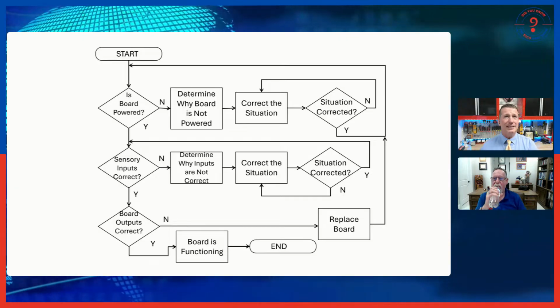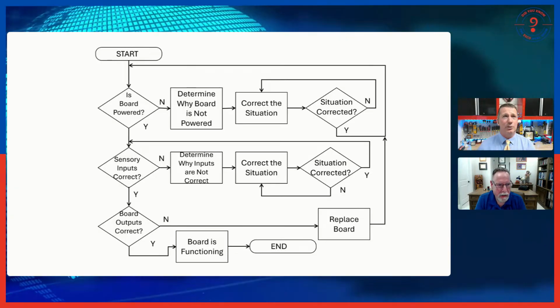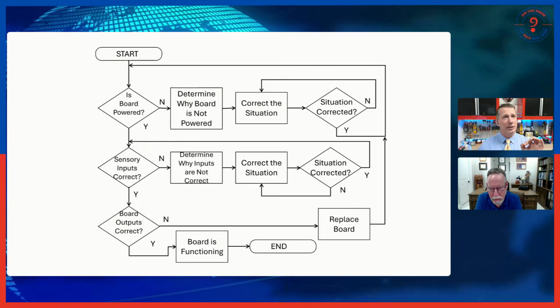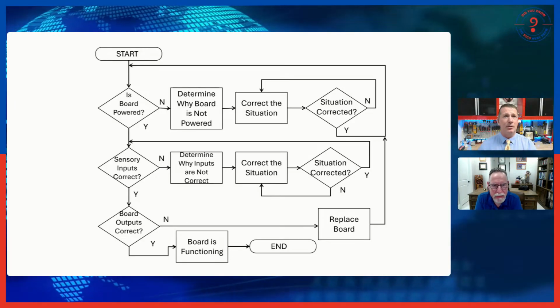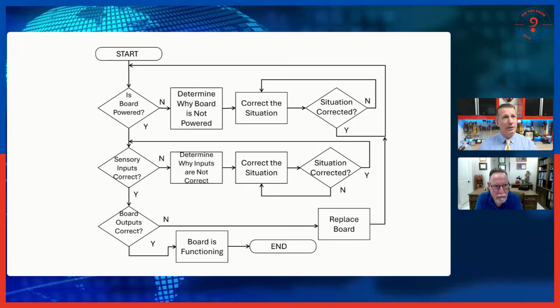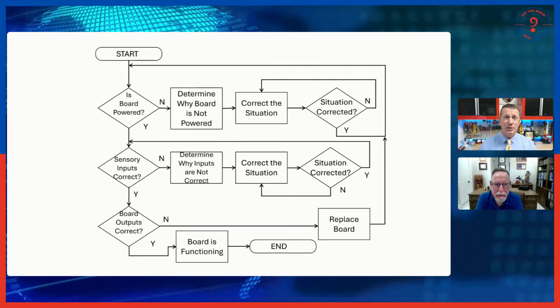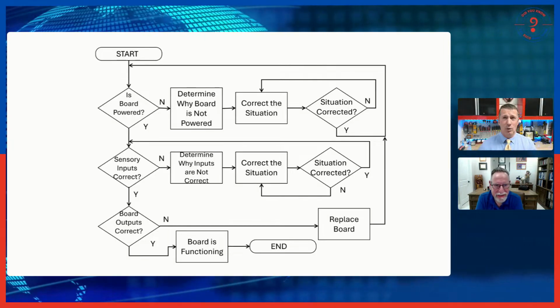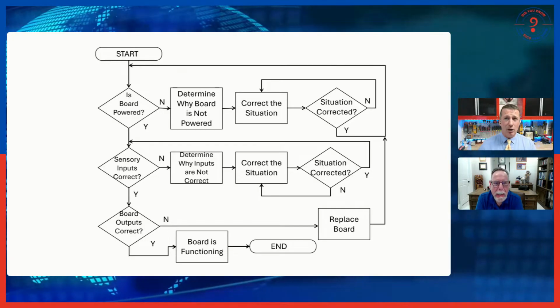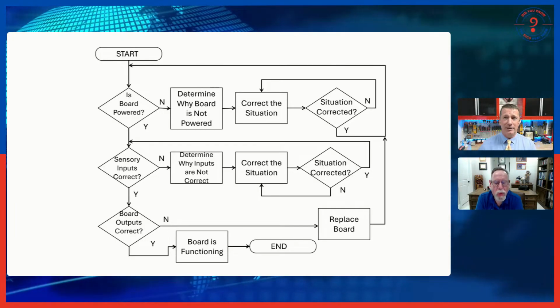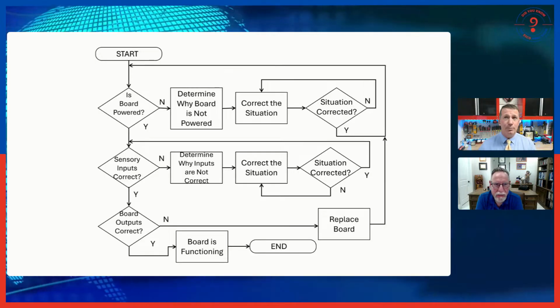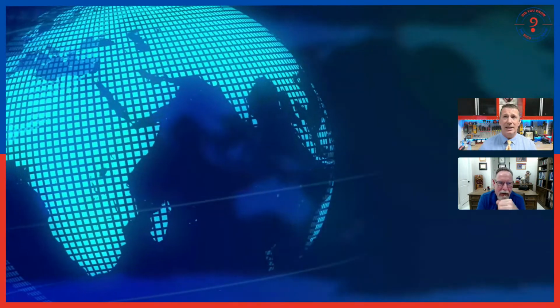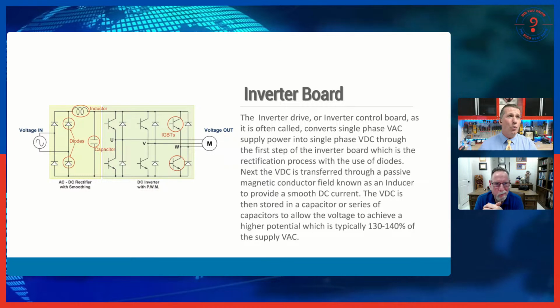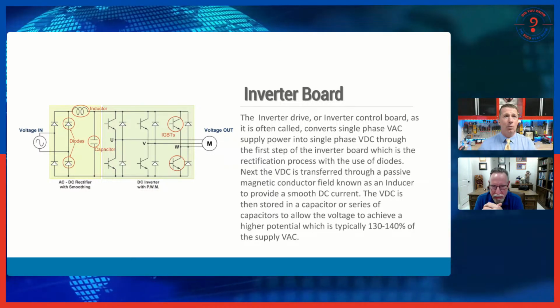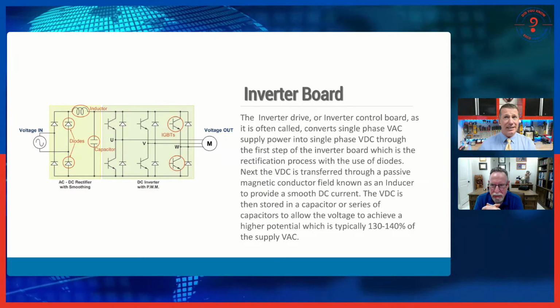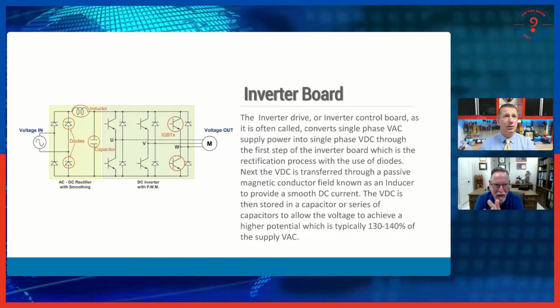So if we take that philosophy and that flow chart, we know we're going to be looking for input voltages, output voltages, and sensory inputs. The beauty of most inverters is that if it's already run once and gone through commissioning, it already understands what those input values are. Most are readable through the system, especially if it's a communicating system. So if we look at what voltages we're checking, it's actually very simple.